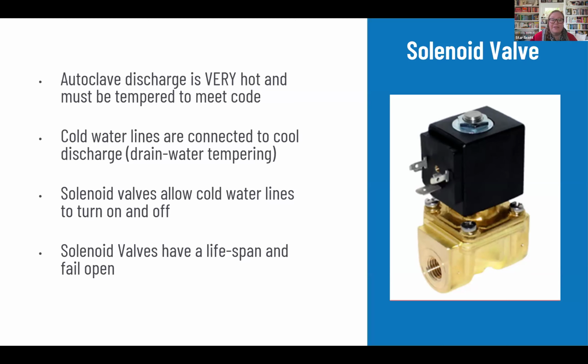But the lifespan of a solenoid valve is between about 5 and 10 years, in comparison to the lifespan of an autoclave, which is around 50 years or more. I mean, we have older ones at our campus. And when these valves fail, they fail open, allowing cold, potable water to discharge down the drain 24/7, 365.